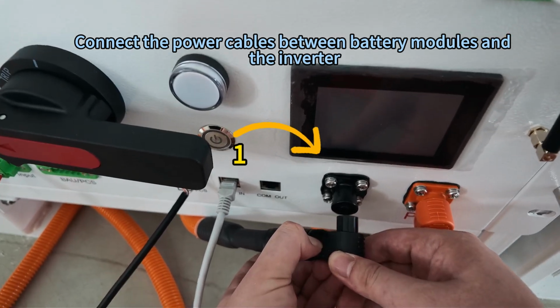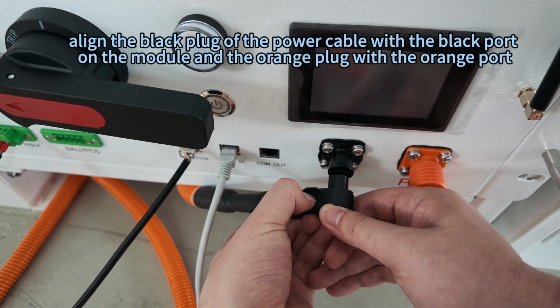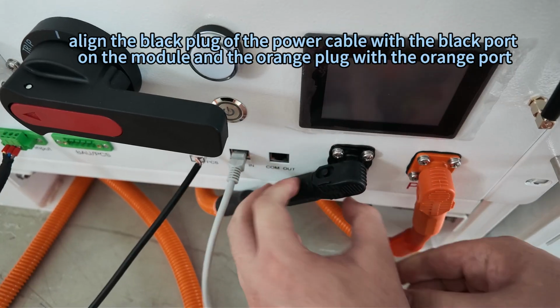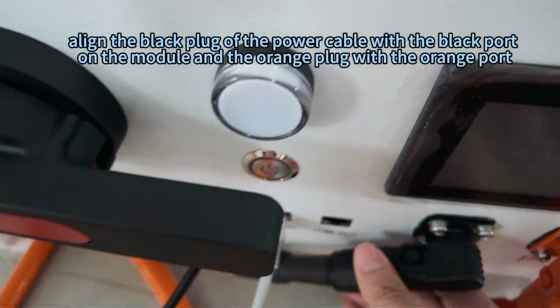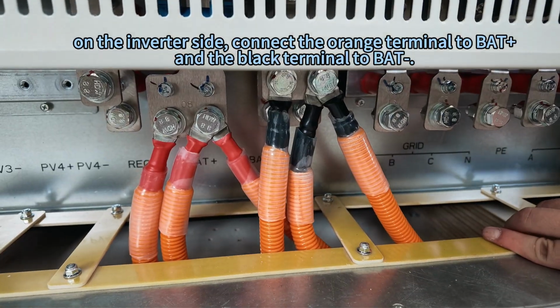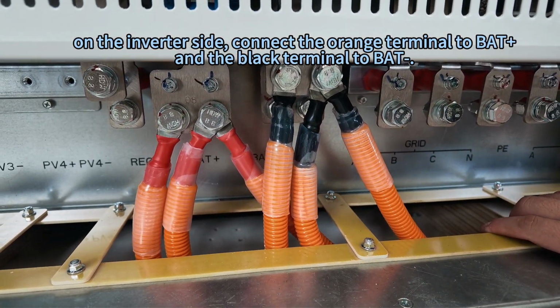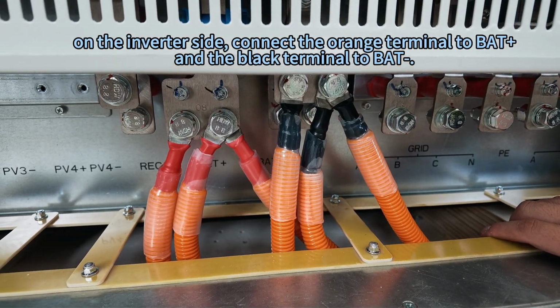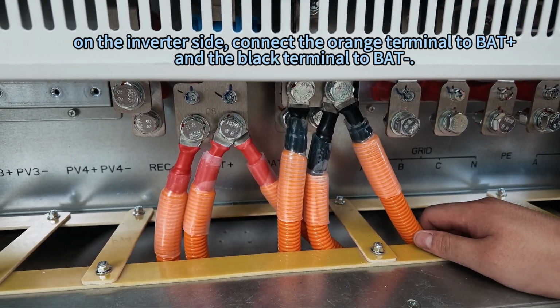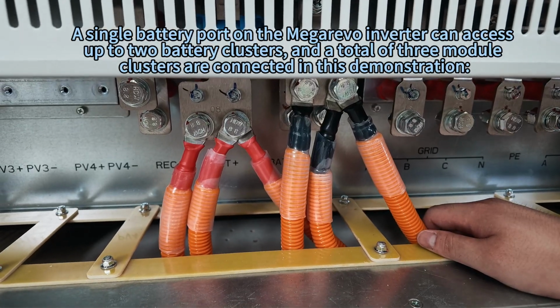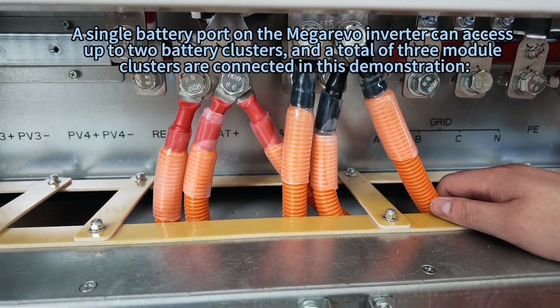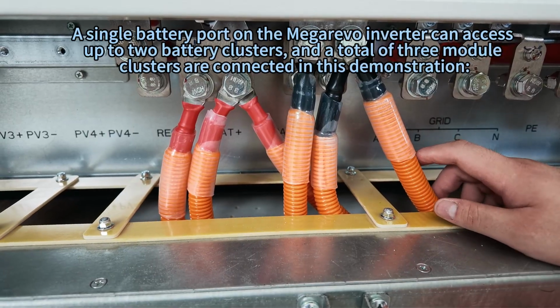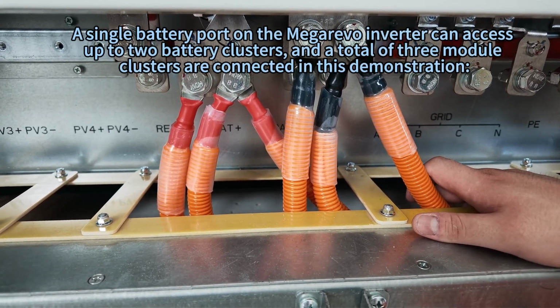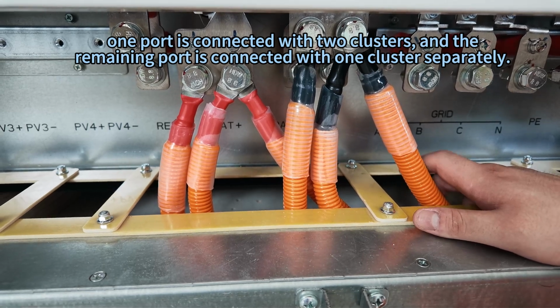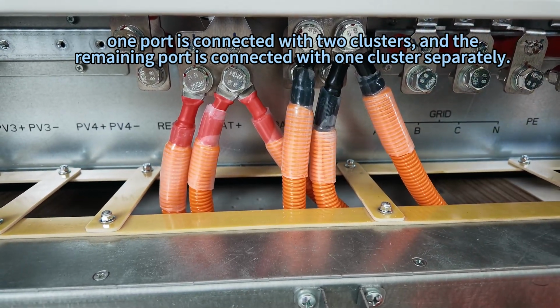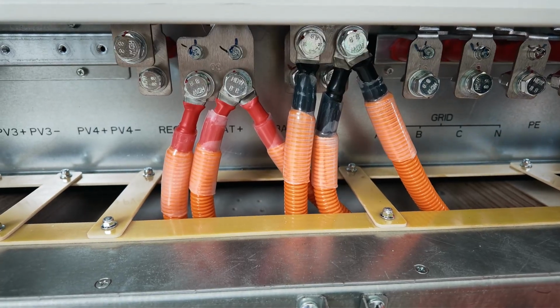Connect the power cables between battery modules and the inverter. Align the black plug of the power cable with the black port on the module and the orange plug with the orange port. On the inverter side, connect the orange terminal to BAT+ and the black terminal to BAT-. A single battery port on the Megarevo inverter can access up to 2 battery clusters, and a total of 3 module clusters are connected in this demonstration. One port is connected with 2 clusters, and the remaining port is connected with 1 cluster separately.